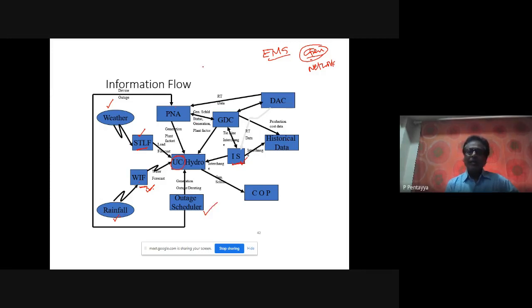Then there's PNA, power network analysis. Under PNA, one important thing in generation control is AGC, automatic generation control. Under PNA, the most important thing is state estimation, where you find the states—voltage magnitudes and angles—which are not directly available from the SCADA data.